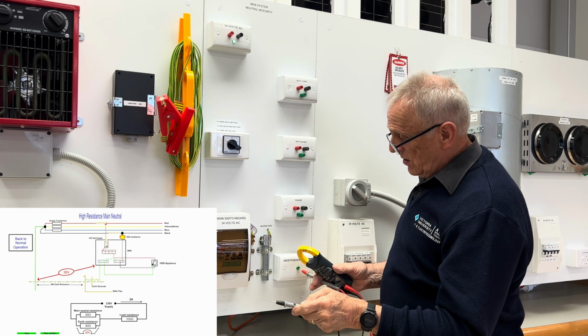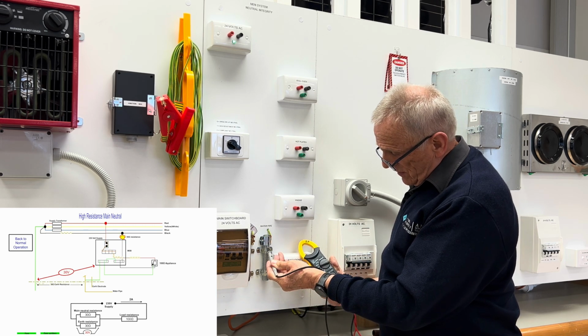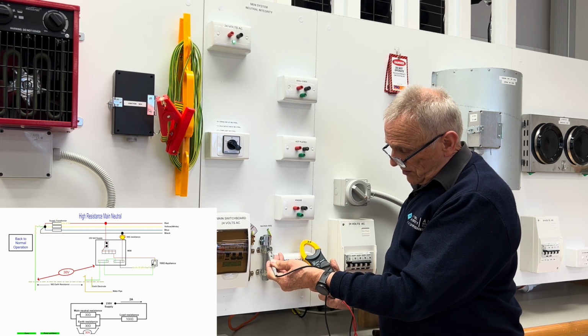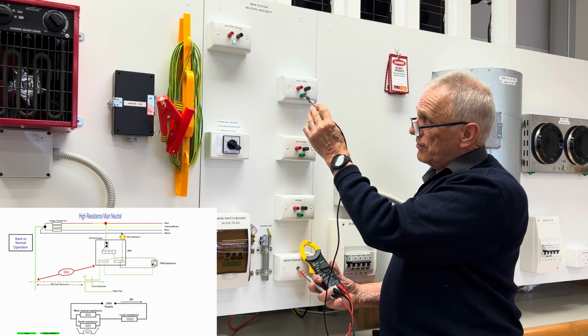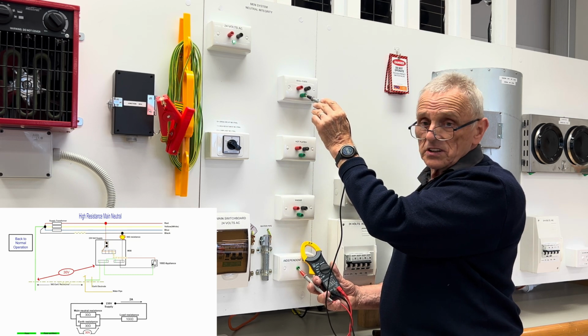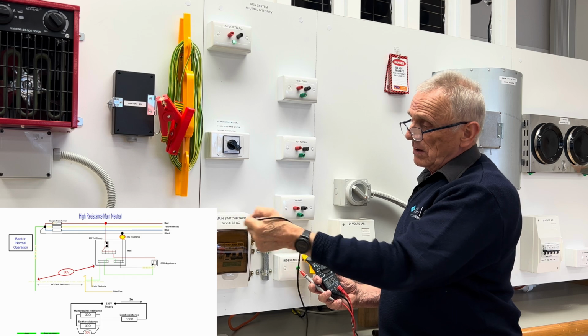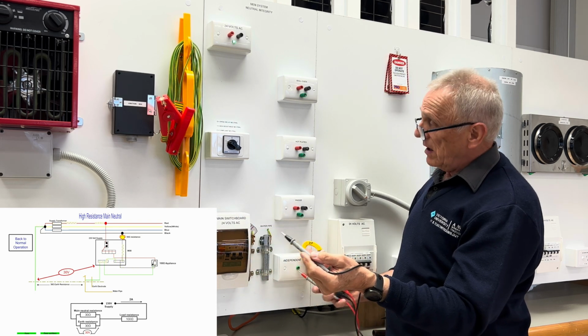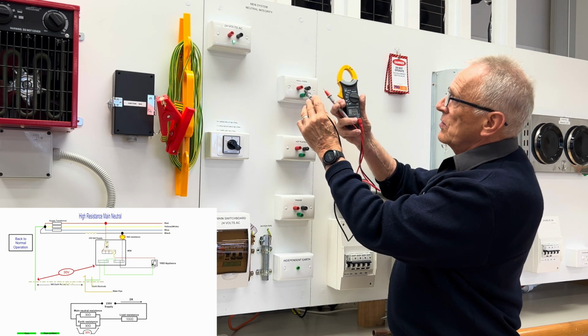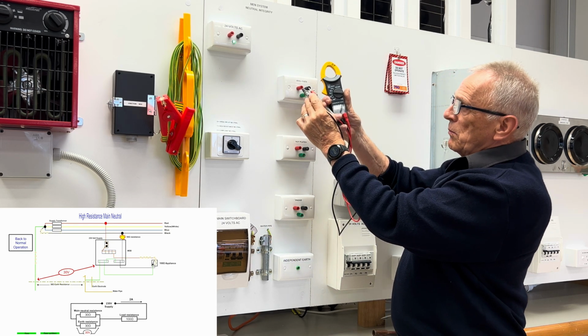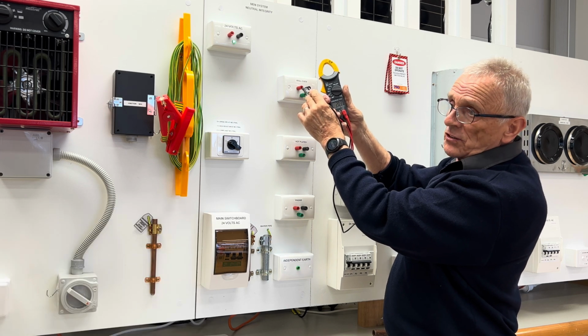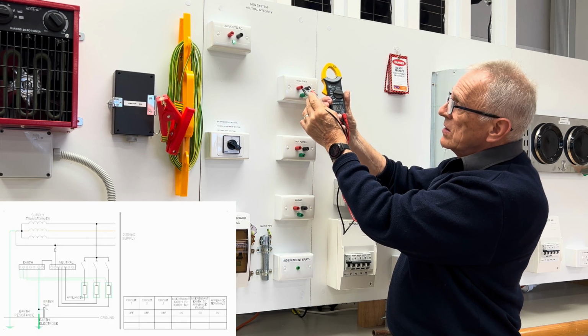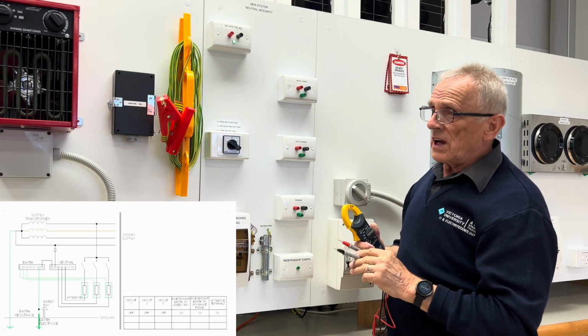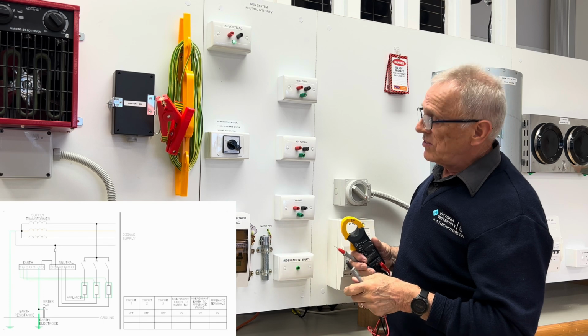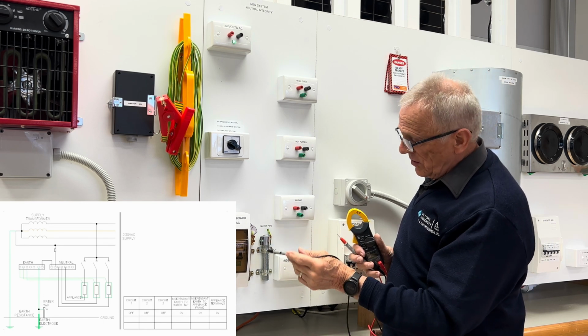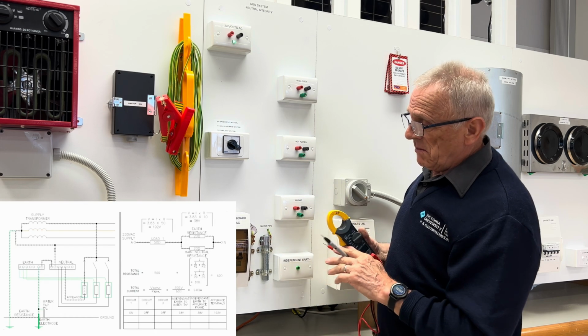and we test from independent earth to the water pipe, and we have a register of 4.4 volts. Now, if we go to the earth frame of the wall oven, we have same voltage because both points are connected to the earth bar or the earth system. Now, if we test across the wall oven, we have approximately 20 volts, which is the remainder of the 24 volts supply. So 20 volts already tells us there's a problem. We have lower voltage across the terminals of an appliance, and we're now getting a higher voltage on the earthing system, which could potentially become much more dangerous.